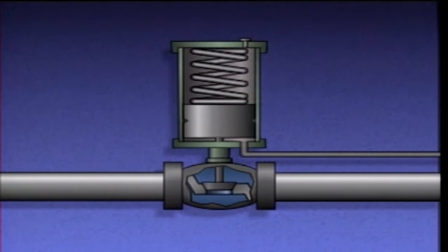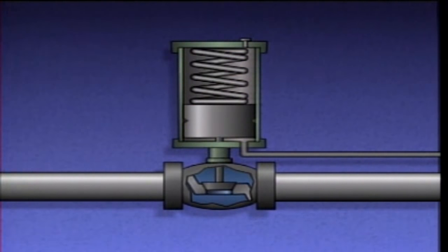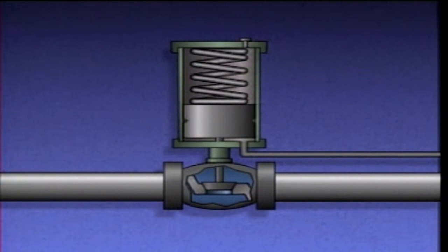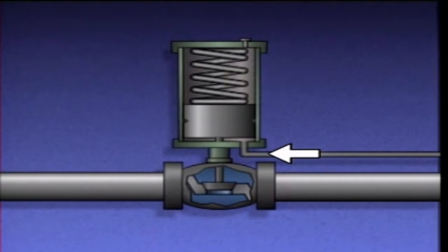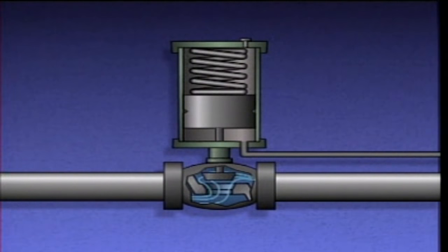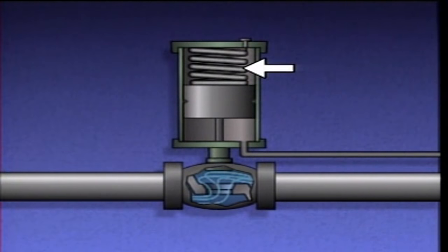A single-acting piston actuator has a controller or similar device that controls the air pressure on one side of a piston. When air is fed through the air supply port, the piston moves along in a cylinder, compressing a spring and opening the valve.